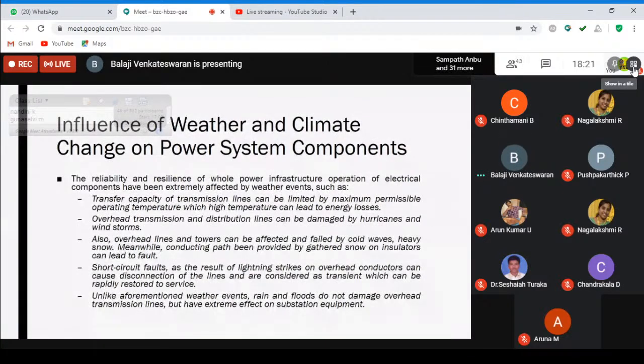As I mentioned, lightning strikes can also induce faults, and that also comes under natural disaster. These points are essential to focus on because they affect the power system components. So the last point: unlike the weather effects mentioned, which do not damage the overhead lines, the substation equipment will definitely be damaged. As I said, the transmission lines are really safe compared to the distribution lines and the substations.